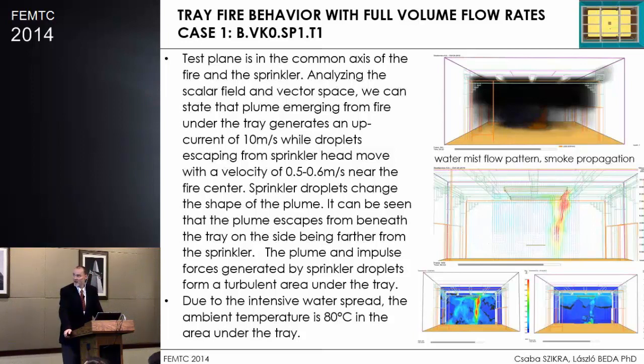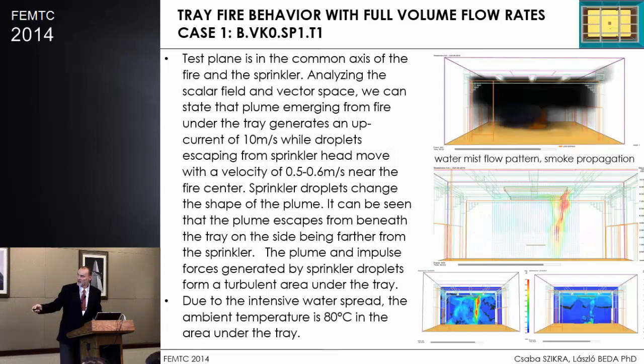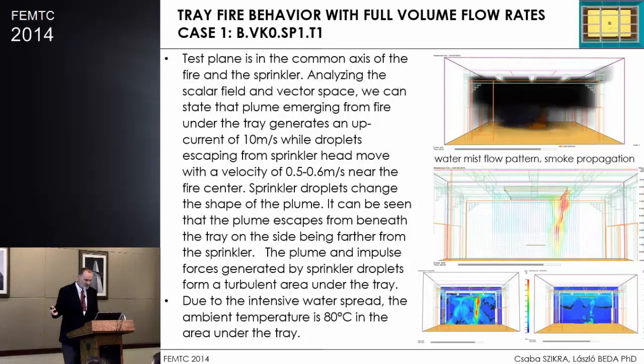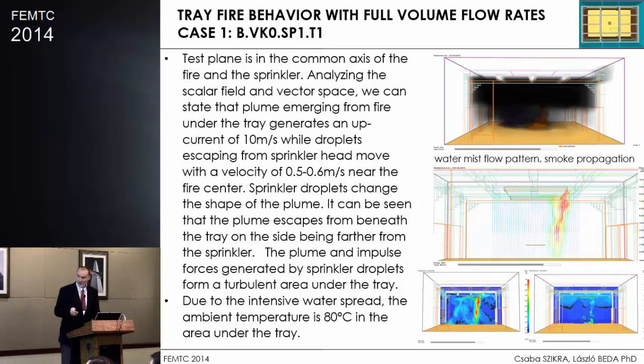In the next set of cases, we introduced a fire — a t-squared fire around 1 megawatt. Based on that, a plume develops. Here is the fire source, and the plume comes up the other side of the shelf element where the sprinkler is. It's quite interesting that the plume is affected by the sprinkler. The plume velocity is around 10 meters per second, and around the shelf the sprinkler velocity is about 0.5 to 0.6 meters per second. The temperature on the tray, due to the cooling effect, was around 80 degrees Celsius.